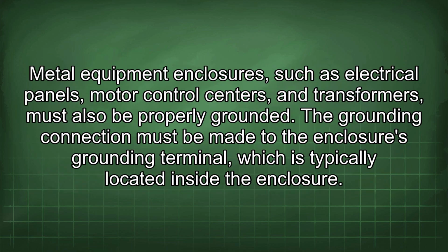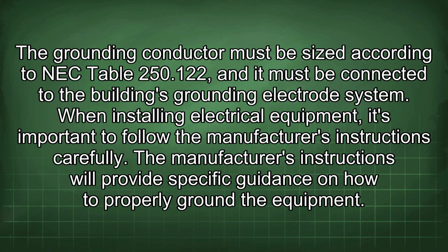Metal equipment enclosures, such as electrical panels, motor control centers, and transformers, must also be properly grounded. The grounding connection must be made to the enclosure's grounding terminal, which is typically located inside the enclosure. The grounding conductor must be sized according to NEC Table 250.122, and it must be connected to the building's grounding electrode system.